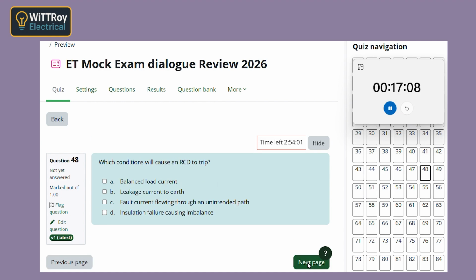Question 48. Which conditions will cause an RCD to trip? Leakage current to earth, I think? Yes, that's one. Let's build the whole picture. If current leaks to earth, then current leaving on the active is no longer equal to current returning on the neutral. That imbalance is what the RCD detects. So it doesn't matter exactly where the current goes, as long as it doesn't return normally. Correct. That's why fault current flowing through an unintended path is also right.